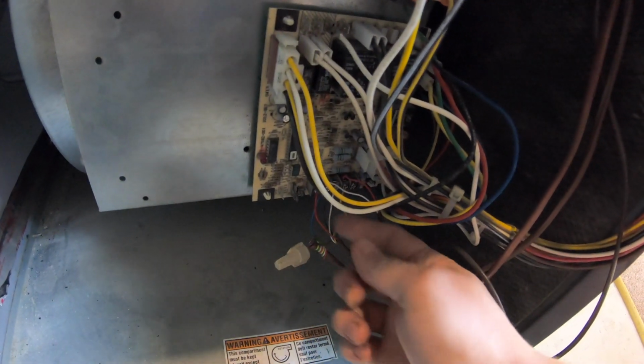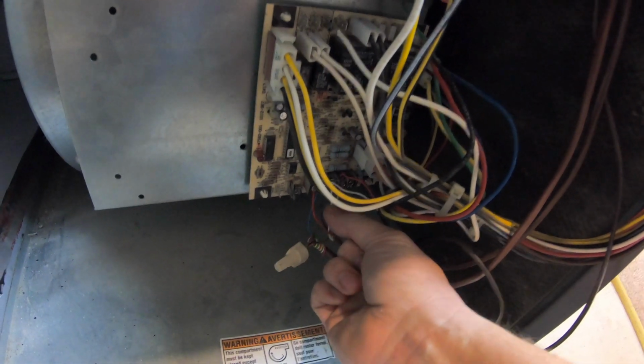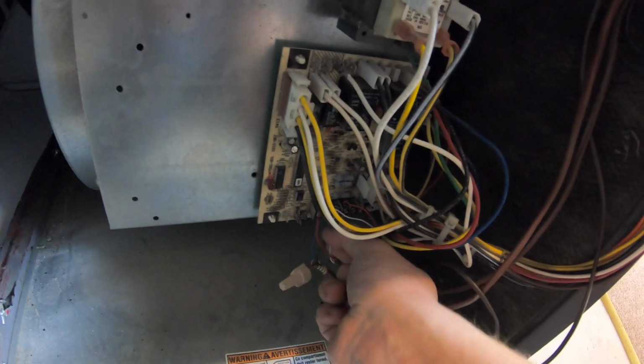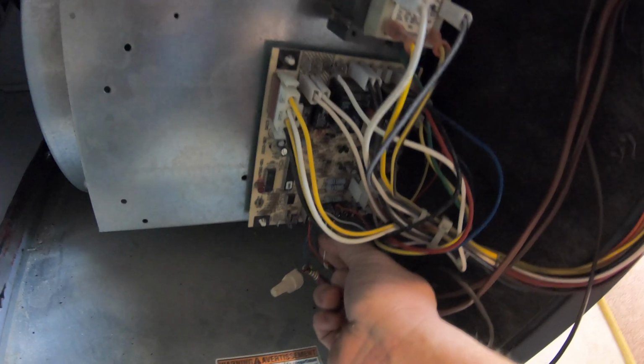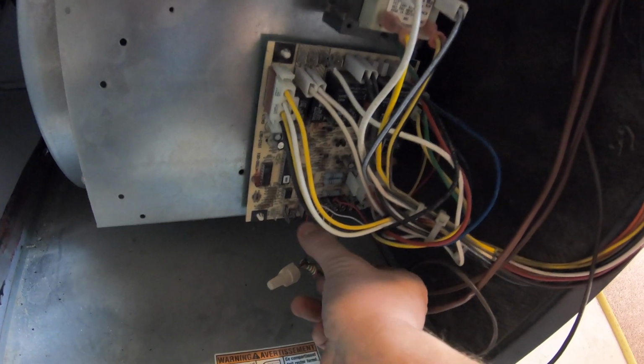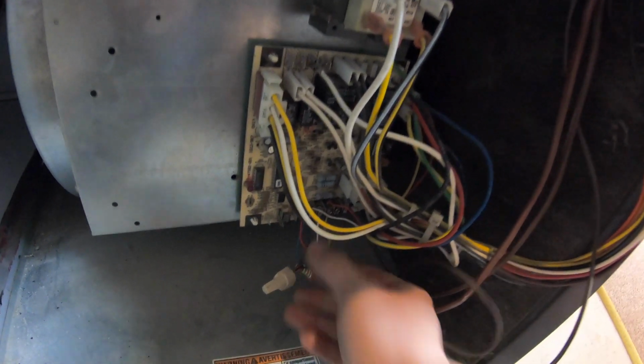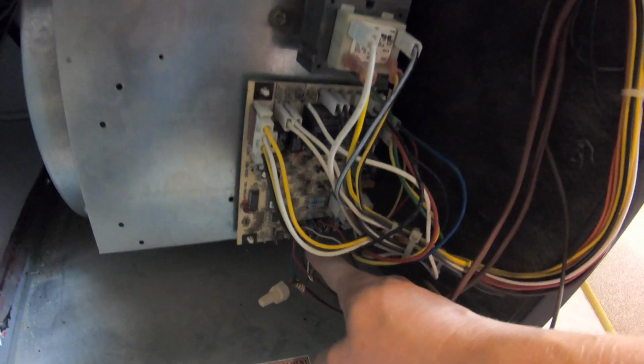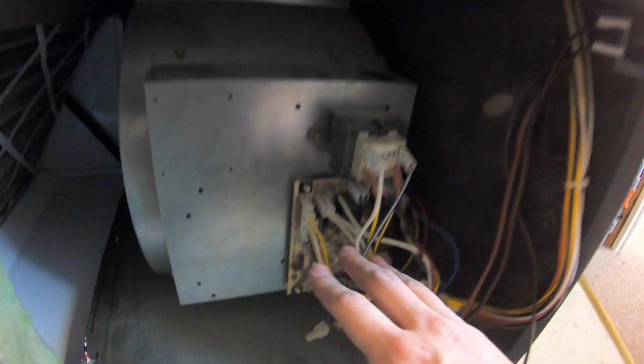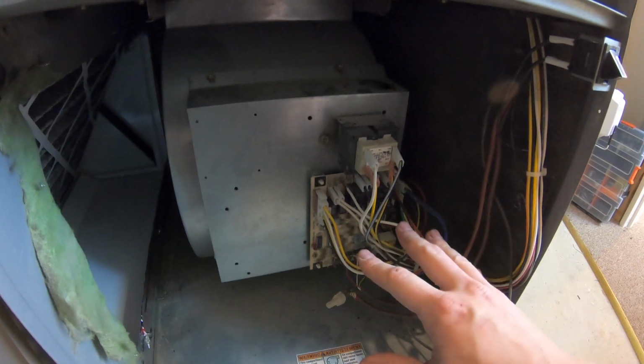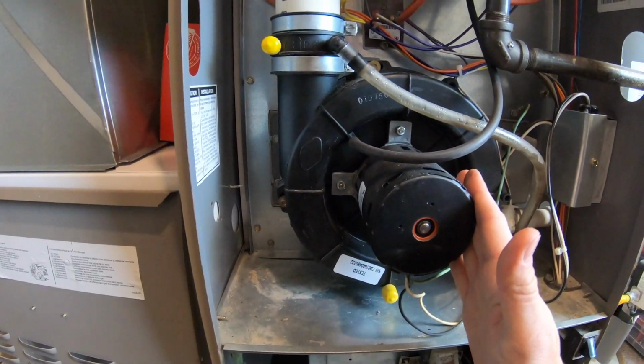Now, this board, when it's on, is sending 24 volts up to the thermostat on this red wire here, and when there's a call for heat, it sends 24 volts back from the thermostat to the circuit board through this white wire here to the W terminal, from R through the thermostat to W. If you're getting 24 volts back to this W terminal, then the circuit board knows it's time to start the call for heat. So the next thing that starts is this inducer motor will start to run.